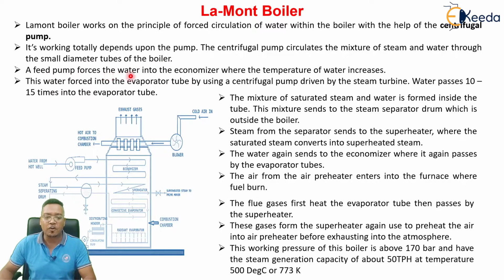The feed pump forces the water into the economizer where the temperature of the water increases. You see here, this is the feed pump and this feed pump is taking water from the hot well, and now this feed pump is feeding the feed water to the economizer. And in the economizer, this feed water will be preheated. Okay, now this water flows into the evaporator tubes by using a centrifugal pump driven by a steam turbine, and water passes 10 to 15 times through these evaporator tubes. The mixture of saturated steam and water is formed inside the tube.